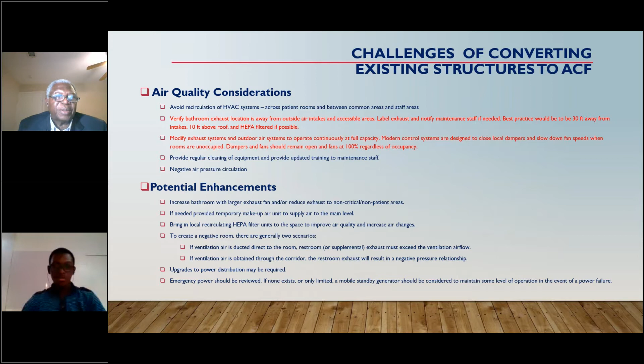Also, we must ensure that the intake of fresh air and the discharge of contaminated exhaust air are kept apart by about 30 feet, and that the discharge is at 10 feet above the roof. It's also recommended that before it is discharged, a HEPA filter is installed on the line. This will also help to reduce contamination when the wind is taking the air around. The modification of the outdoor system is very important for continuous operations, and control systems must be properly designed to meet what is happening, with dampers properly closed.